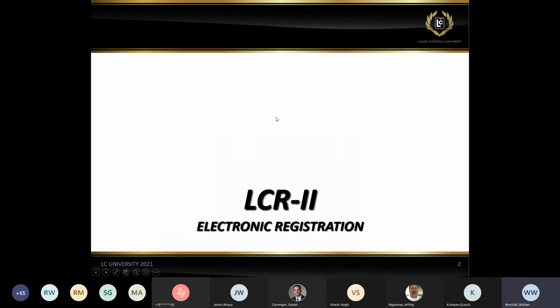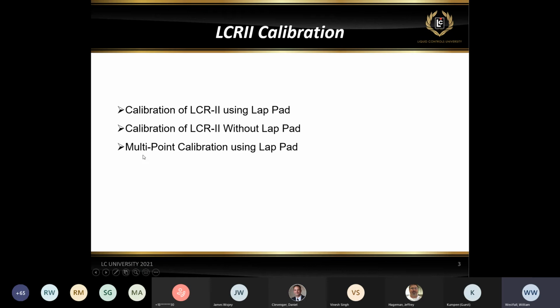So moving on to the LCR2. We're actually not going to talk too much about multi-point calibration here today, because that could be a discussion that takes hours on its own. So we're going to talk about calibration of the LCR2 with the lap pad, and then calibration of the LCR2 without the lap pad. And for any of those out there wondering about calibration with the 600 on the lap pad, keep in mind that the LCR 600 does not have lap pad functionality. So you can only calibrate the LCR 600 through the front display and keypad, or you can use Easy Command, which I'll show you towards the end of the hour.